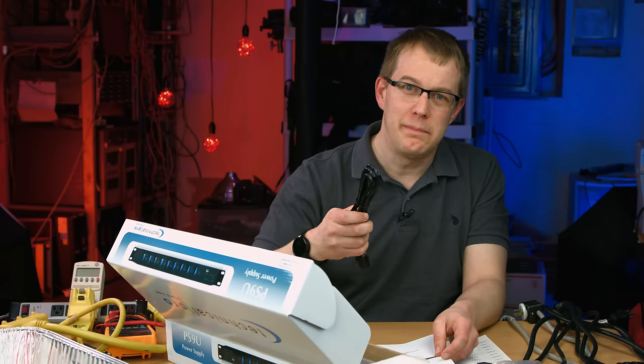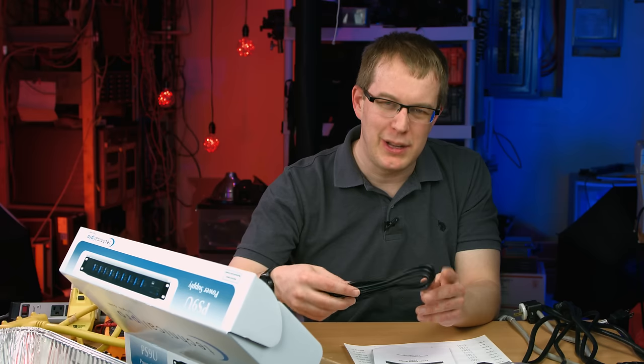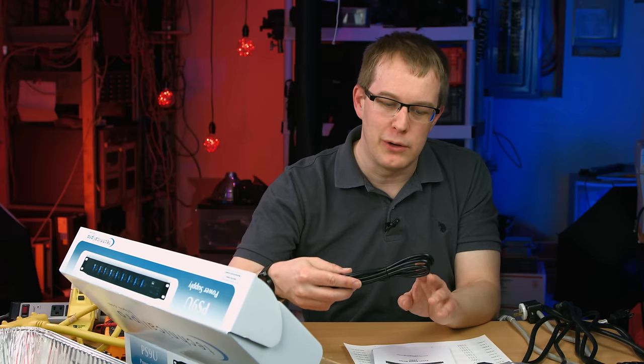But if this thing is only rated at 10 amps, then this cord is fine. It's a 10 amp cord. So for example, if the PDU had a 10 amp breaker or 10 amp fuse in it, I would be okay with this cord. I wouldn't be super happy because it's the very bare minimum of what you could possibly have.